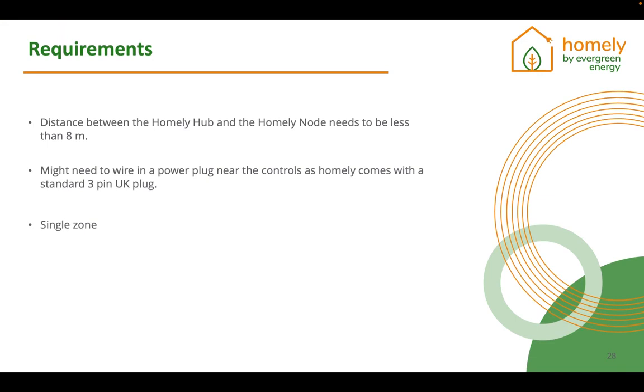In terms of the installation of the Homely, there are a couple of requirements at the moment. You need to make sure that the distance between the Homely hub and the wireless temperature sensor, which we call the Homely node, is less than 8 meters. This is a limitation of the radio that we're using at the moment. It will be improved in the future. At the moment, you just need to make sure that that distance is maintained so that you don't have issues with node disconnections, so the temperature sensor losing signal to the actual Homely hub.